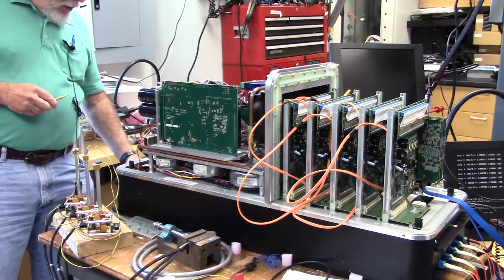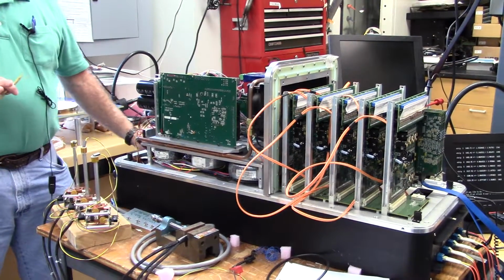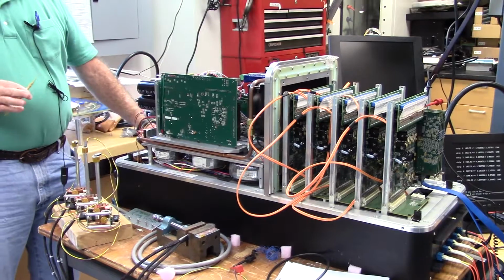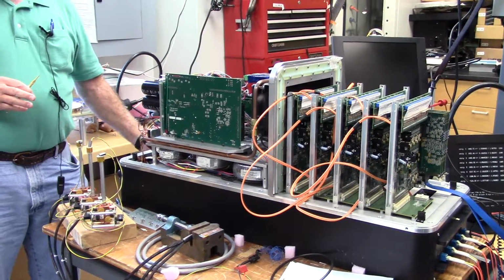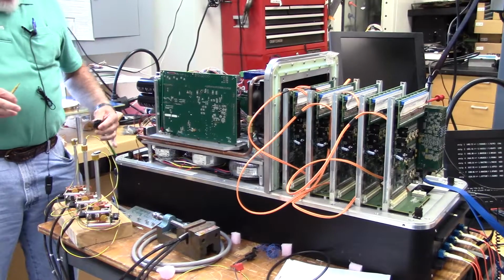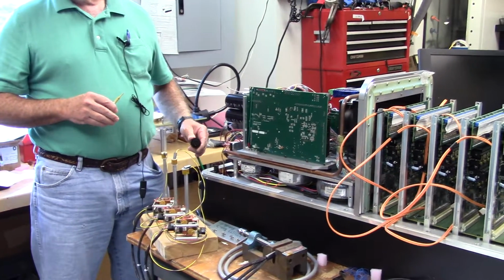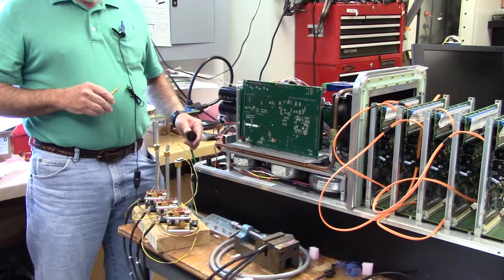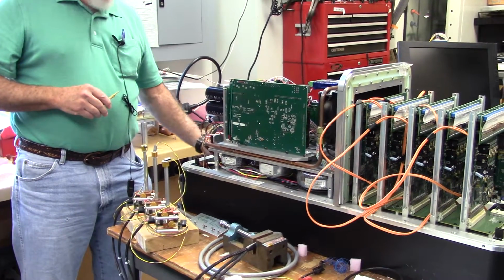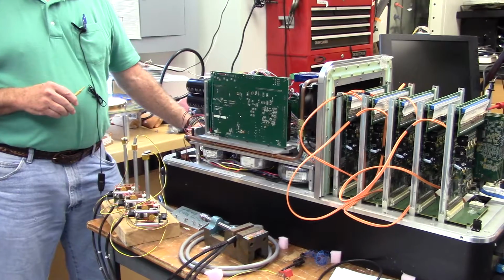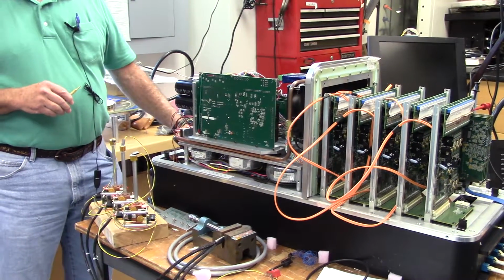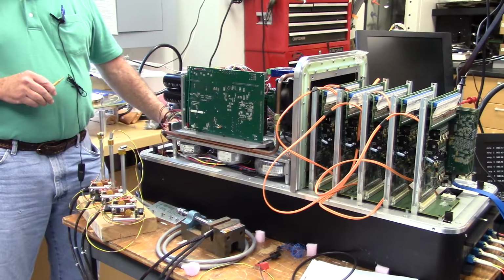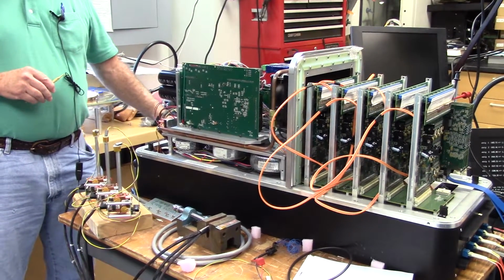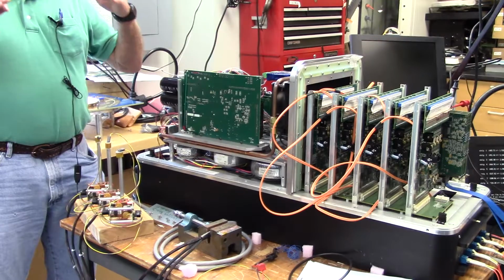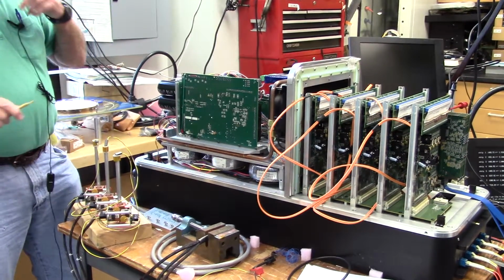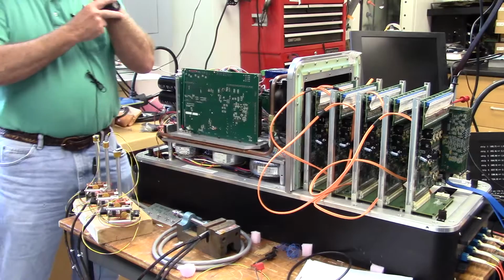So that's how power gets into the HE. There is no power switch on the HE. So if you need to turn the HE off, you either have to disconnect this connector, which I do from time to time - it's kind of poor form because you always produce a little arc on those poor gold contacts - or you can give the command to the APC strip in the computer rack, normally on outlet number 4, or there is a switch on the rack that contains the isolation transformer, and you can always shut it off with that too.